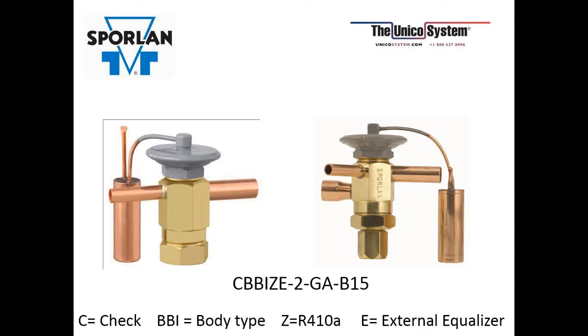The Z is a refrigerant code. In this case, Z equals 410A, and R22 would be a letter V, like in Victor. It's a very important thing to check, guys. I know we pretty much made a 100% switch to 410A, but we were asked this very often, whether they had a 410A or a 22 valve. So there's your answer right there. So Z is 410A, then V is R22. The 2 in this case indicates it's a 2-ton valve. We always tell you the tonnage of our valve, not the BTU rating. It's an actual tonnage.